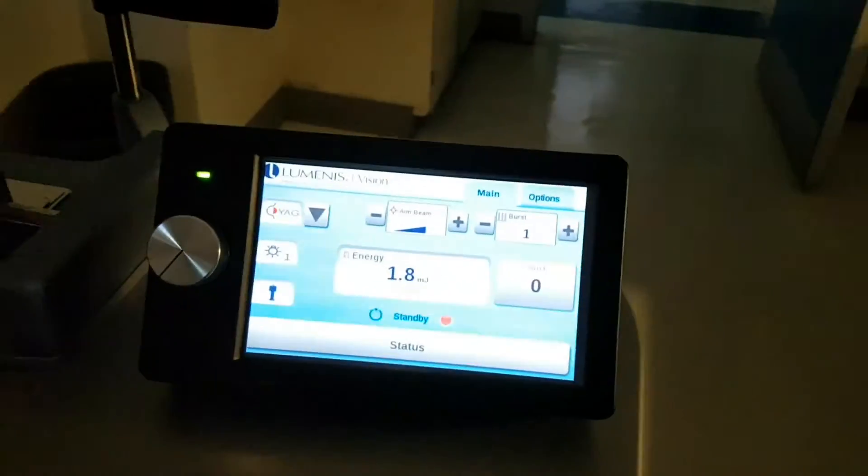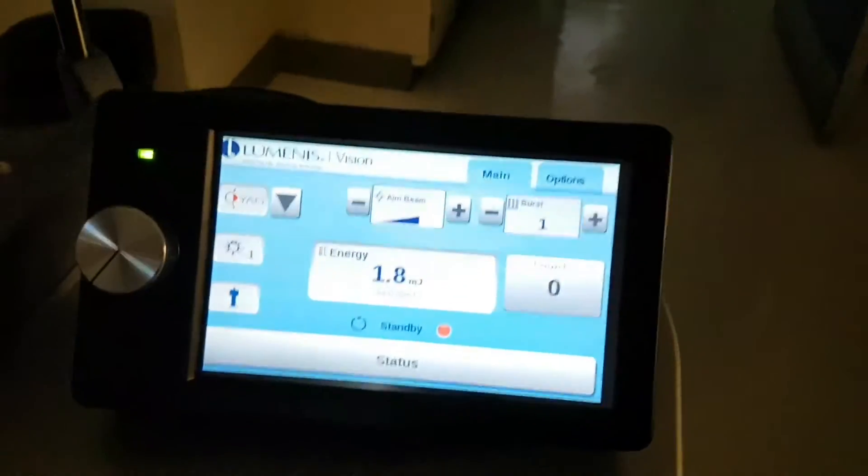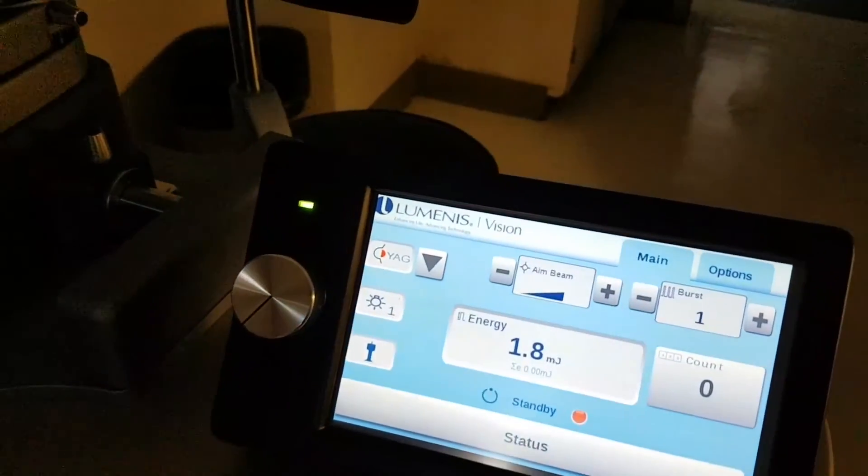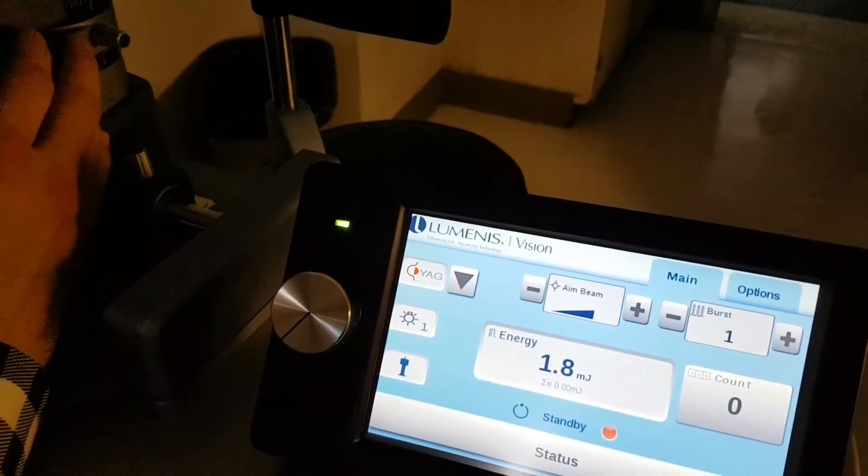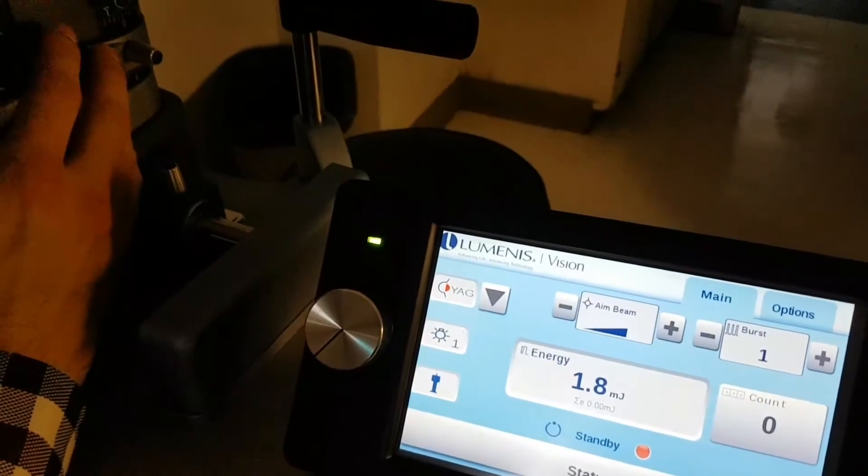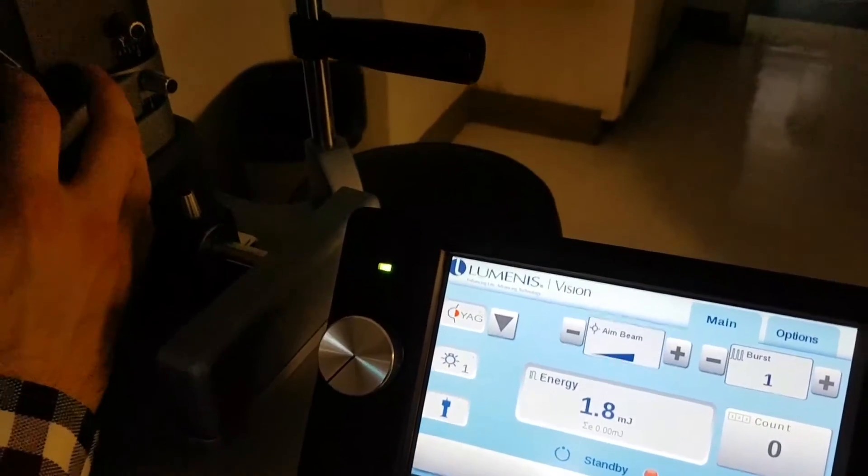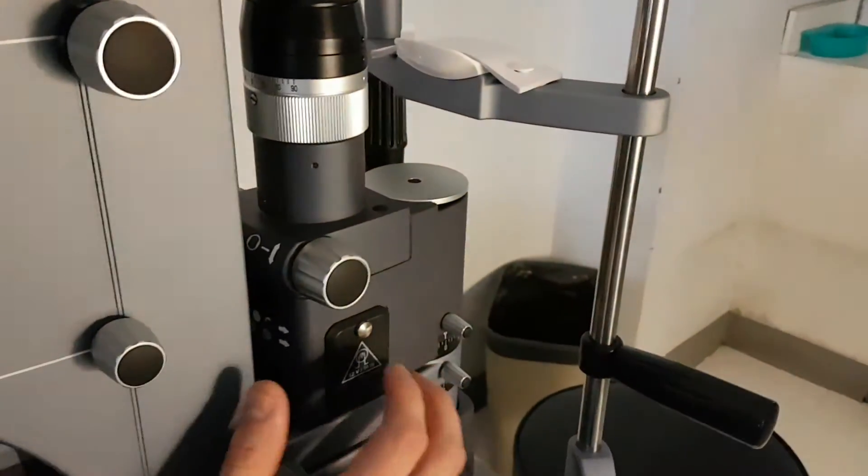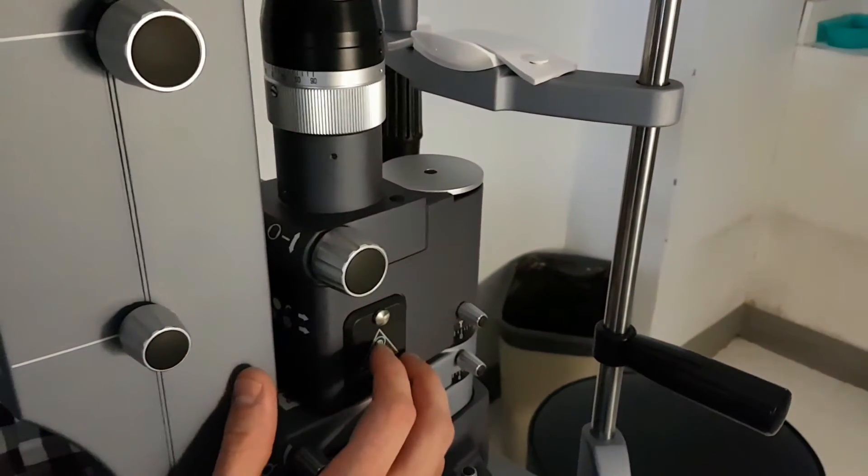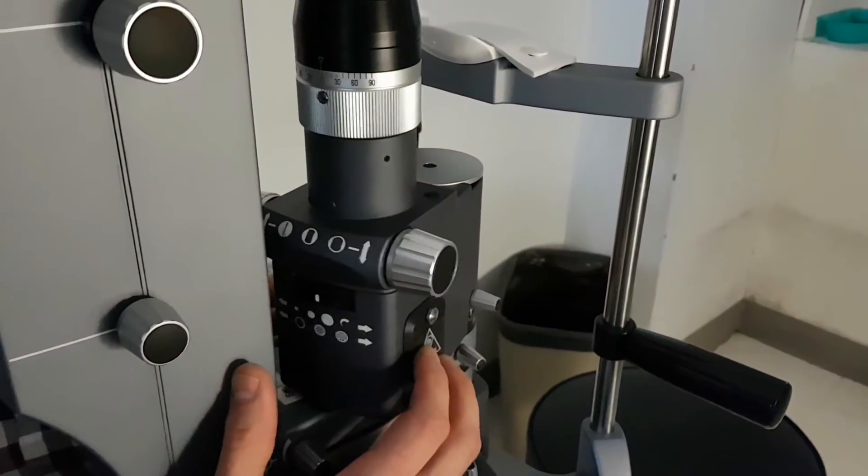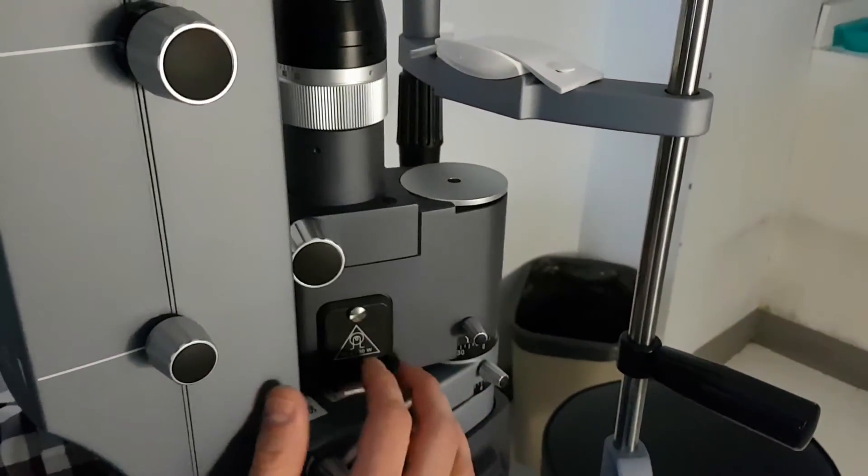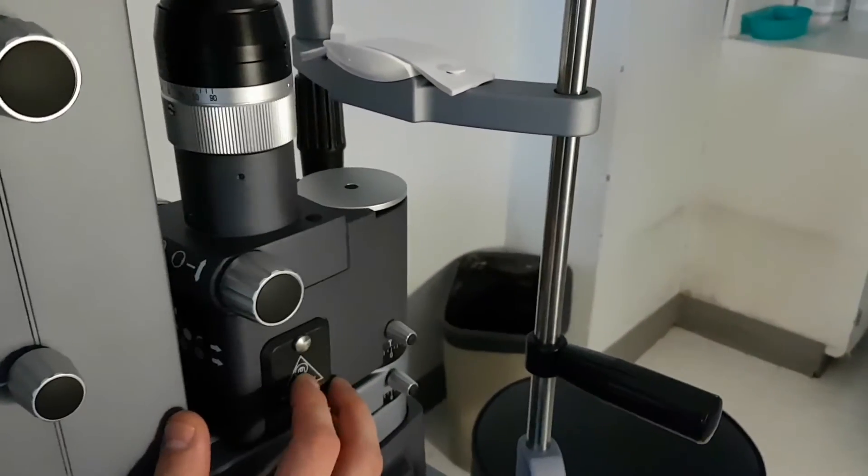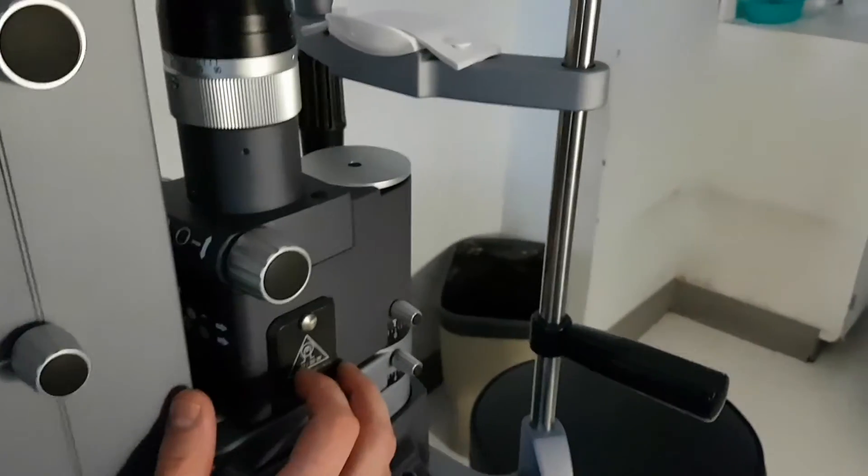If you're using the YAG laser, the main thing you have to watch out for if the laser isn't working is the position of the slit lamp. If the slit lamp is directly in front of the laser, you will have a message here that indicates move illumination tower.